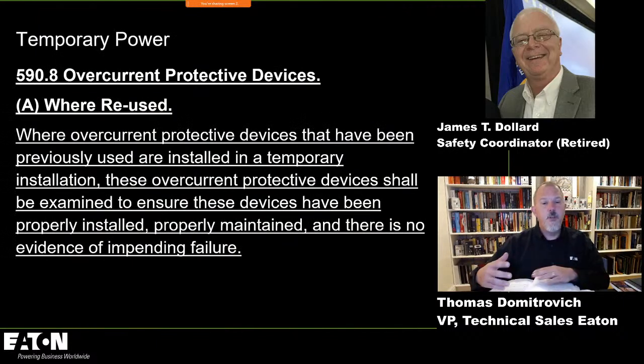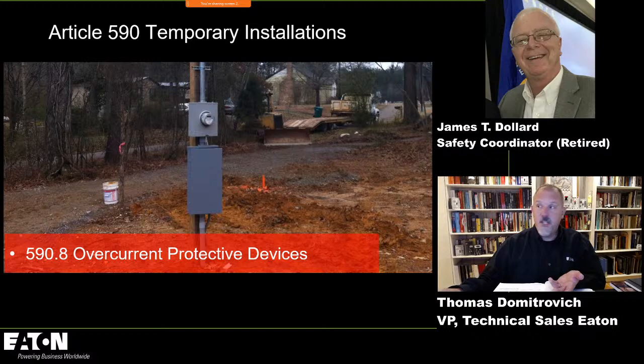Yeah. And then in 590, they put in a new requirement that says for temporary power, when you're reusing overcurrent protective devices, you have to inspect them, and they use the term no evidence of impending failure. I think that was because when you're getting into temporary power, you'll get equipment that might end up looking like this, although that's not temporary power. You're going to take a piece of equipment like this and use it at this job site, then at the next job site, and you're going to keep reusing it over and over and over.